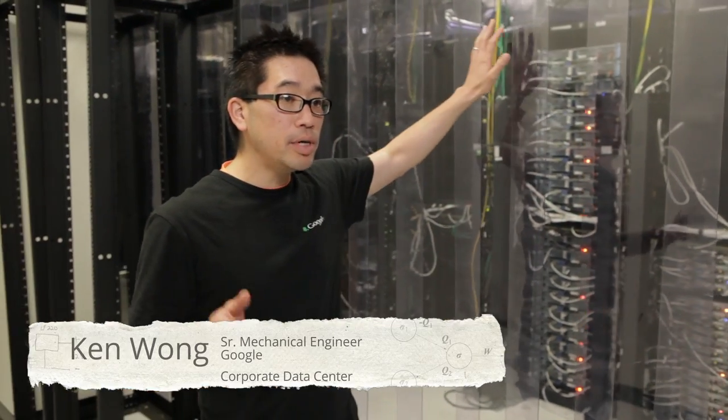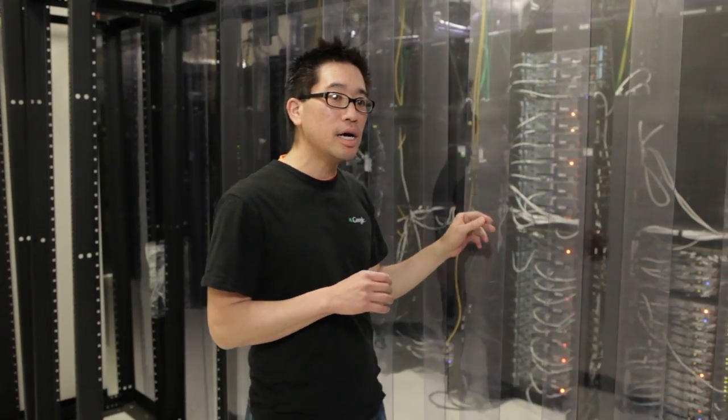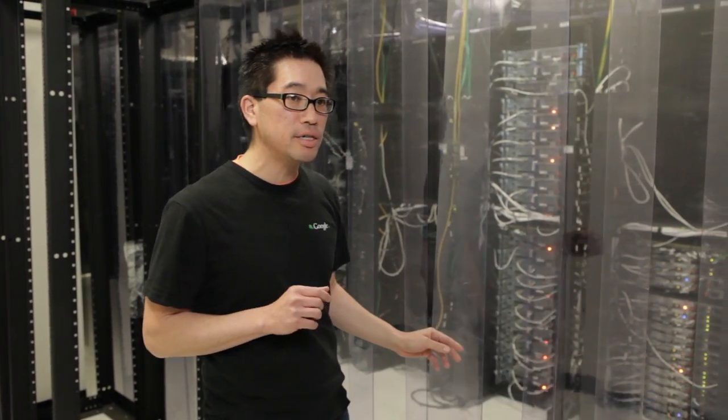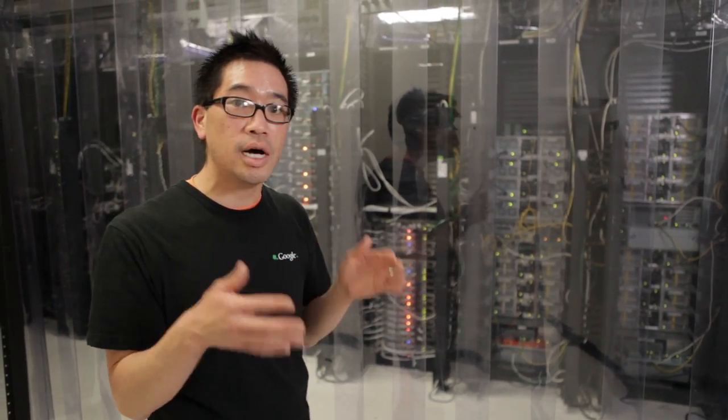We also did a bunch of other retrofits. Here in this corporate data center at Google, we've implemented meat locker curtains that are very inexpensive and easy to install. These are hung from the overhead structure and they separate the cold aisle, which is actually hot, and the hot aisle, which is actually hotter.